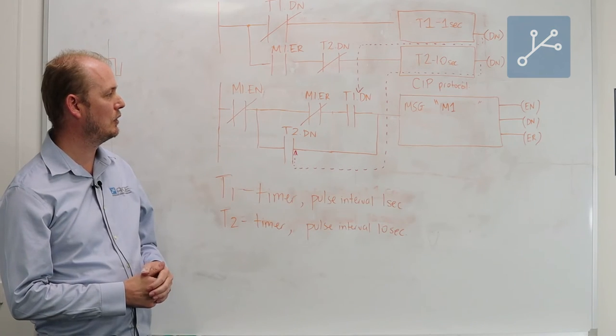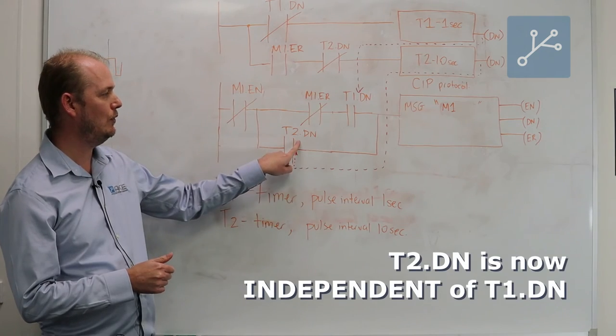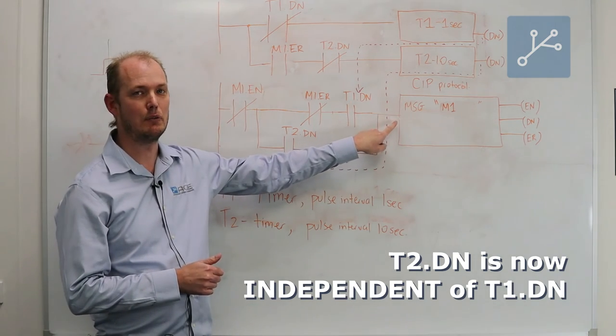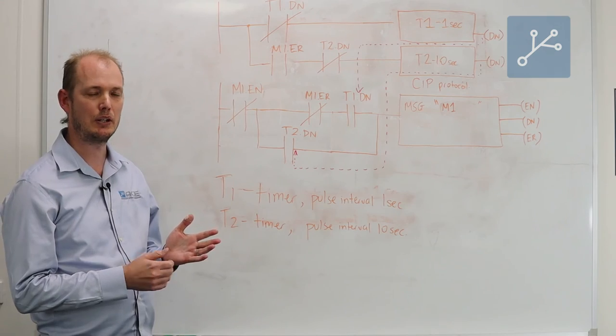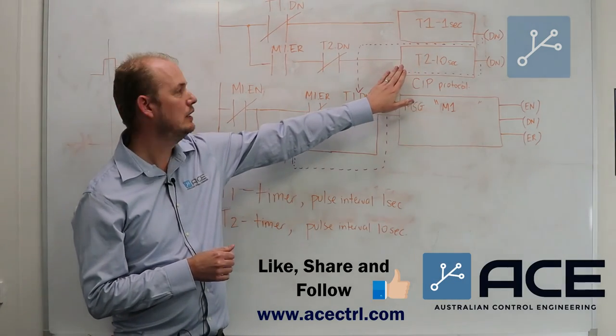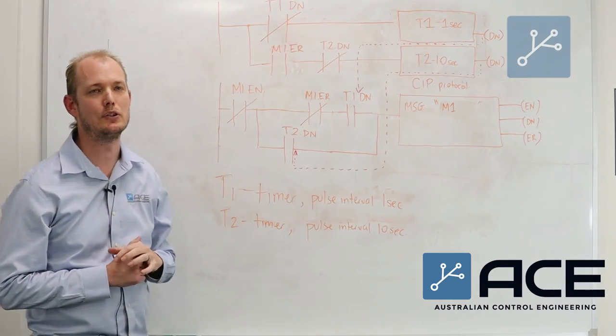So then when there is an error with the message instruction, T2 will separately control the re-execution of the message instruction. Once the message instruction is back to a healthy state, then timer 2 will no longer be needed and timer 1 will again control the execution of the message.